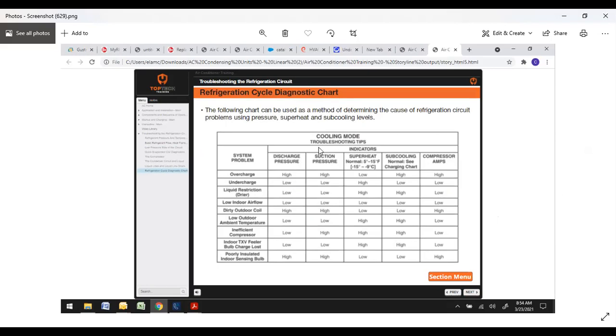So as you get into some diagnostics here, some cooling mode troubleshooting tips. Usually an overcharge is kind of obvious to see. Your discharge pressure will be high. Your suction pressure will be high. Superheat's usually going to be extremely low. And then your subcooling is going to be high. And your compressor amperage is going to be high because you got too much refrigerant in the system. A lot of those you can just see within a couple minutes what's going on.